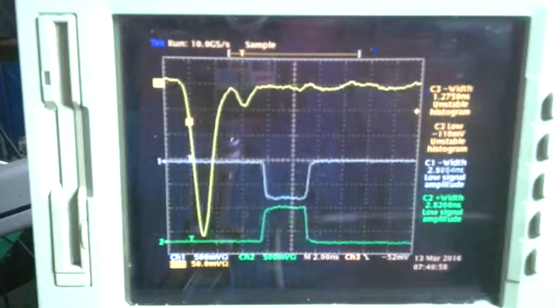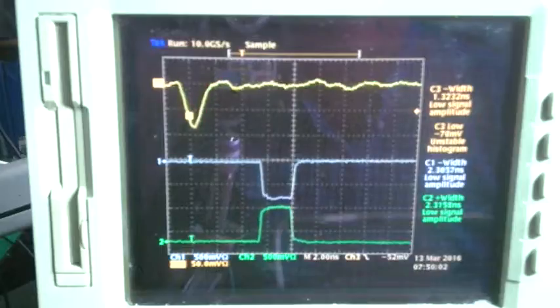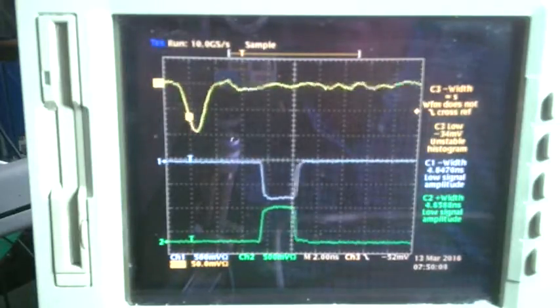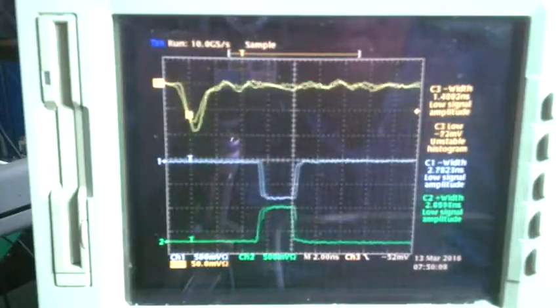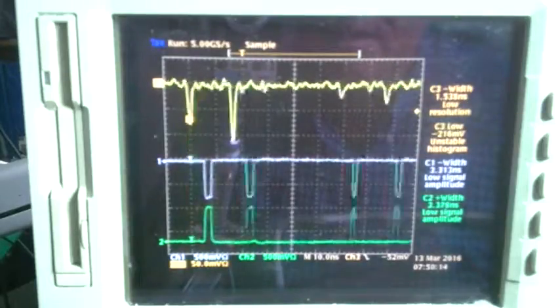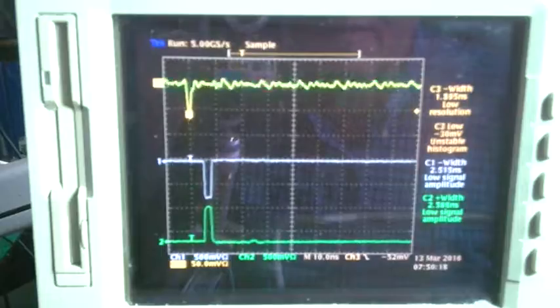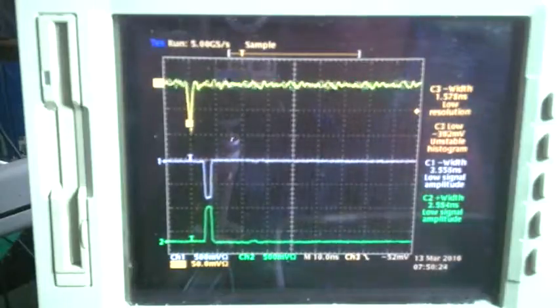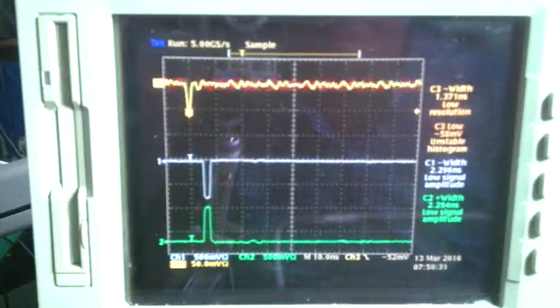The reason that the output pulse width of the limiting amplifier is not fixed like it is with some other discriminators at 10 nanoseconds is it allows one to see a second pulse which might occur within 10 nanoseconds. Occasionally there will be a second pulse that occurs within 10 nanoseconds of the first one. If that's the case, then you would totally miss this if the pulse width were fixed at 10 nanoseconds. Also, having a variable pulse width which is proportional to the amplitude of the photomultiplier output will allow further processing.